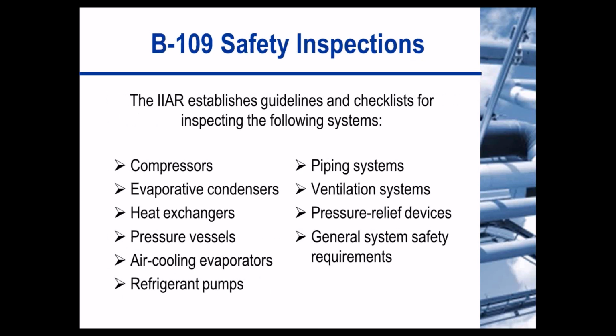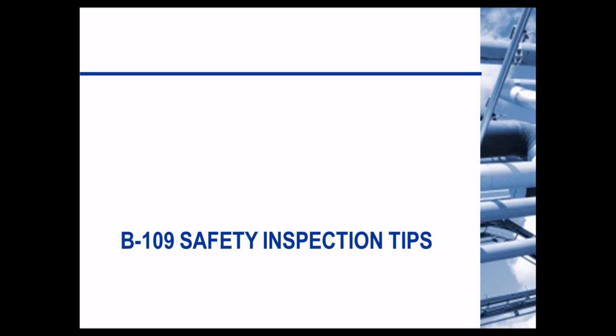So the B109 safety inspections establish guidelines and checklists for the following components: compressors, evaporative condensers, heat exchangers, pressure vessels, air cooling evaporators, refrigerant pumps, piping systems, ventilation systems, pressure relief devices, and general system safety requirements. So let's go into some safety inspection tips.